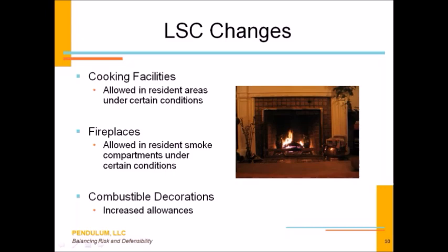But now, again, in pursuit of this home-like environment in our healthcare facilities, particularly our nursing homes, you're allowed to have in your means of egress, in that 8-foot minimum corridor, up to 30% combustible decorations present as long as your building is fully sprinklered. And we know all of our nursing homes are fully sprinklered. Not all of our hospitals are, so you got to take that in consideration because there's a lesser requirement if it's unsprinklered. But let's just talk sprinklered for a second.